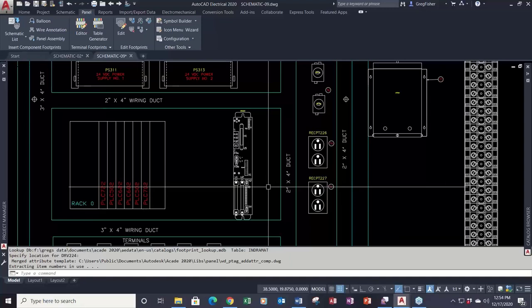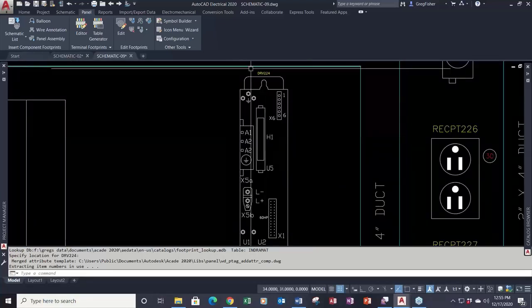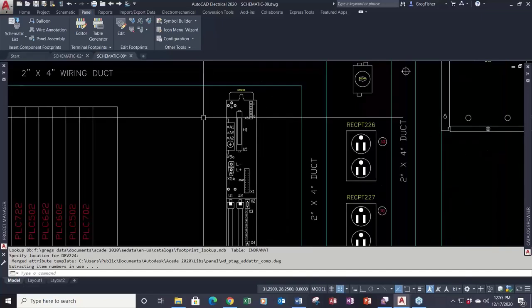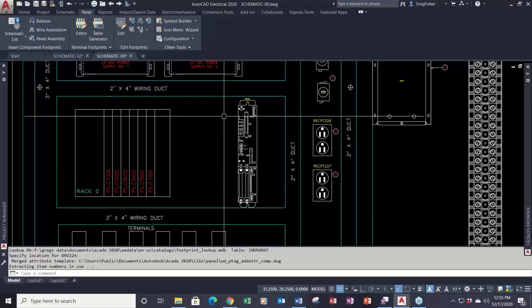If I hadn't linked the footprint symbol I created to the block through the footprint database, it would have no idea what to insert — it would have been stuck. I would have had to go to the icon menu to insert footprint symbols manually. For footprint symbols, all you need is that one tag attribute. That's how we use the symbol builder to create schematic and footprint symbols. On the schematic side, keep in mind the table in the parts database, create the table if one doesn't exist, and that table attribute is the family code in the symbol.